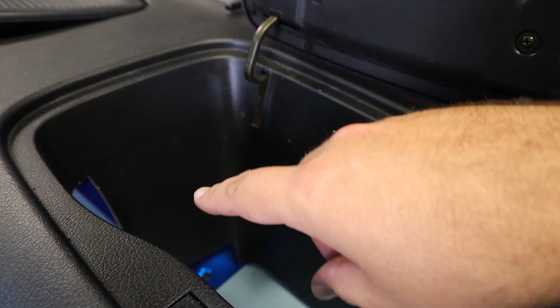This is a couple days later from the last clip, and what I needed to do was pick up some different lugs. I think what I concluded is this one, for instance, said it was for a 1/0 cable, but the overall diameter of that lug is significantly larger. I know this one is open-ended, but I think the issue was the ones on there being too large, which is why they wouldn't fit with these crimpers. I've gone through and verified these all have a stamp of 1/0 on them, and they look like they'll fit just fine in the crimper.